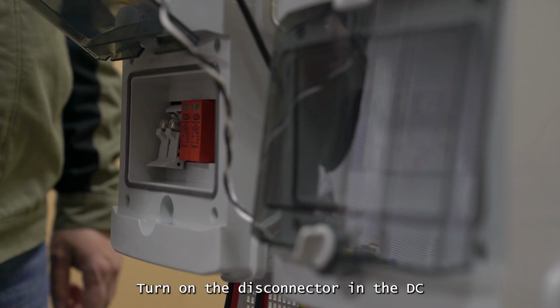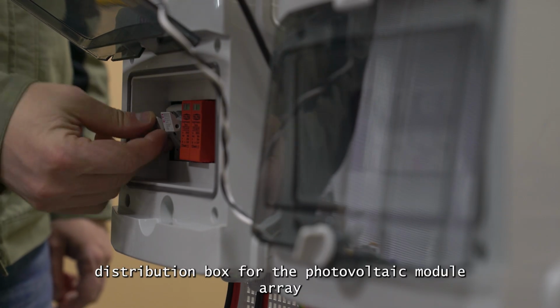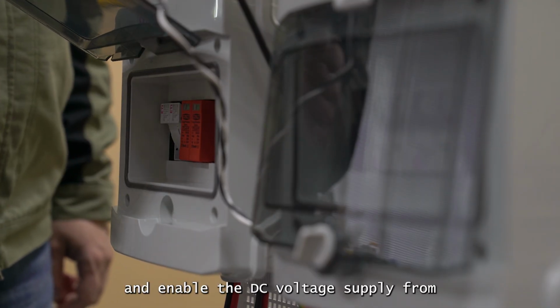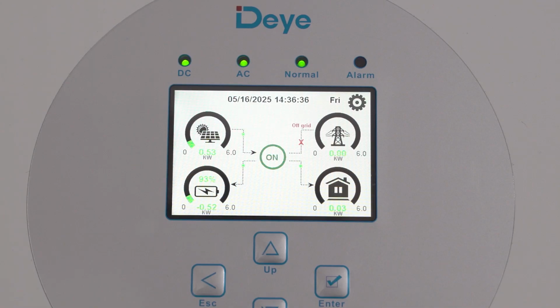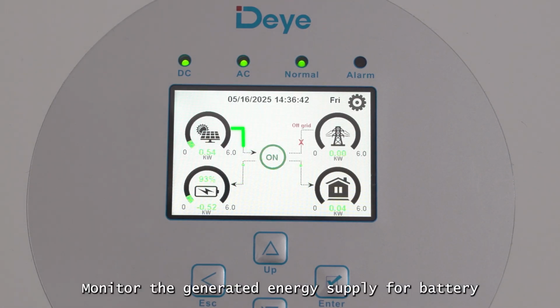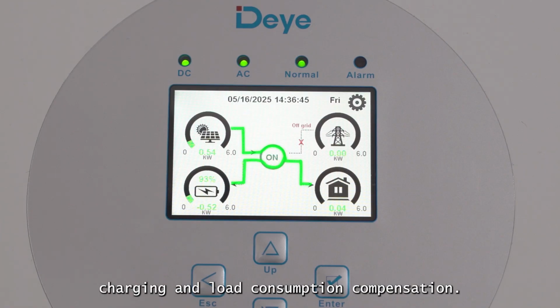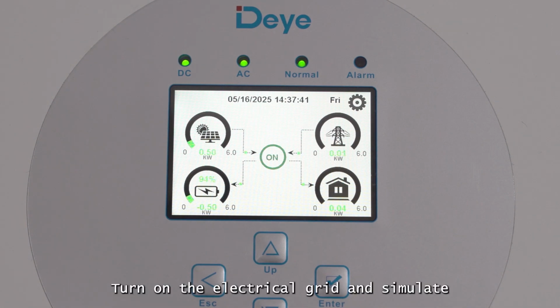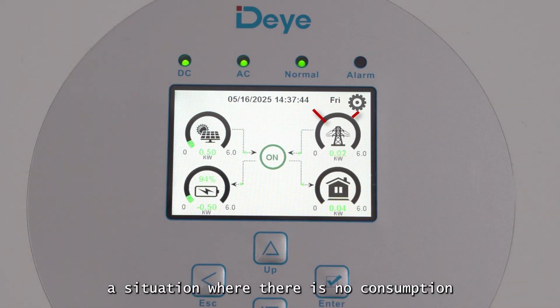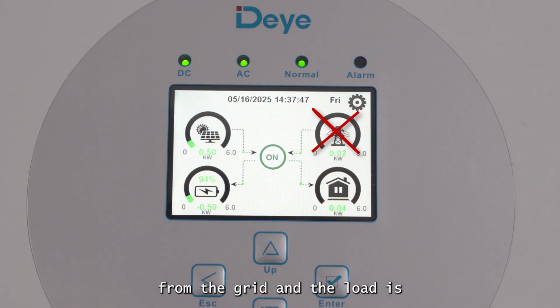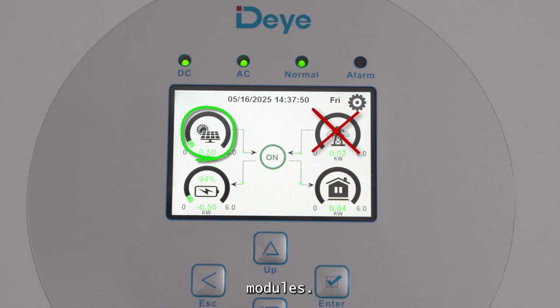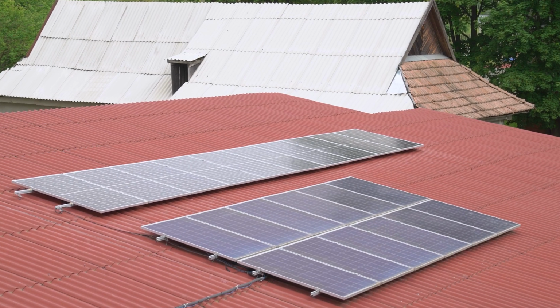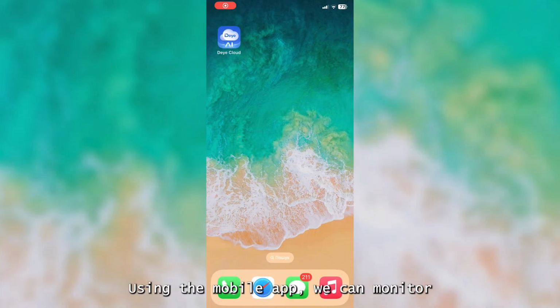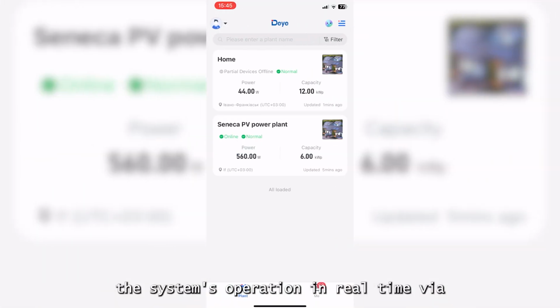Turn on the disconnector in the DC distribution box for the photovoltaic module array and enable the DC voltage supply from them to the inverter. The DC indicator on the panel will light up. Monitor the generated energy supply for battery charging and load consumption compensation. Turn on the electrical grid and simulate a situation where there is no consumption from the grid and the load is powered by energy coming from the photovoltaic modules. Using the mobile app, we can monitor the system's operation in real time via online monitoring.